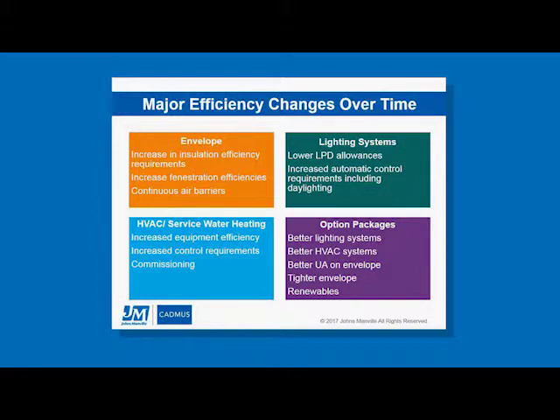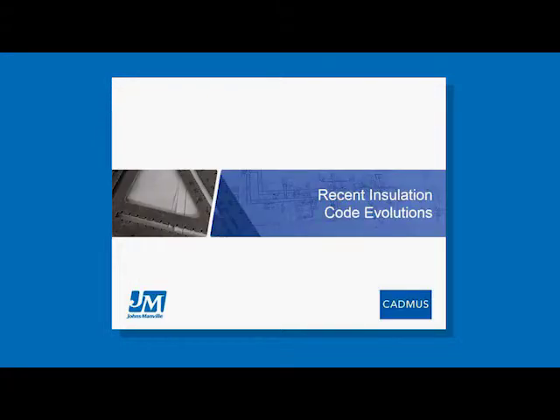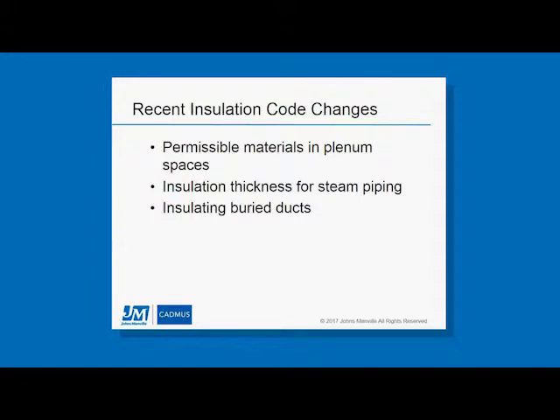With the code changes, what I'd like to do is touch on several examples of the implications for code change, how it has an impact both on manufacturers like Johns Manville and other insulation manufacturers, as well as contractors installing those products, and architects and engineers that have to design within those spaces. The first example is materials that are permitted in a plenum space and how the code language has changed for that. The second example will be the increase in insulation thickness for steam piping. And the third example has to do with insulating ducts that are buried in attic or ceiling insulation.